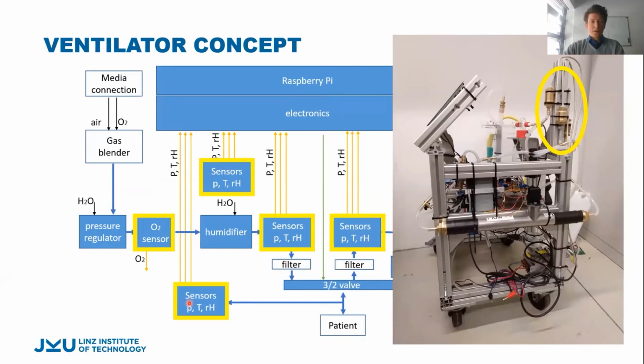At each of these 4 locations there are 3 sensors measuring pressure, temperature, and humidity. So we have 3 times the same values at each location, and this redundancy is used for error correction. We can take the median of the 3 sensors, and if one dies, the other 2 still have valid values so it keeps working. At the same time, we can set an alarm to tell someone to replace the whole module, which just means plugging it out and plugging in a new one.